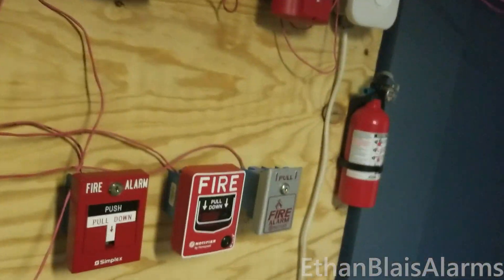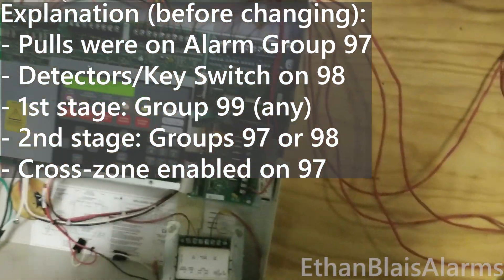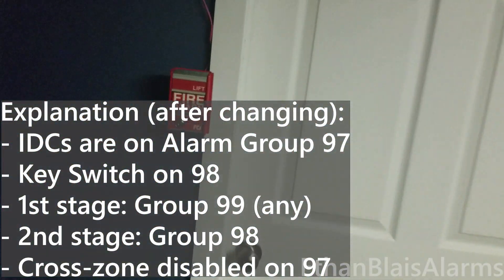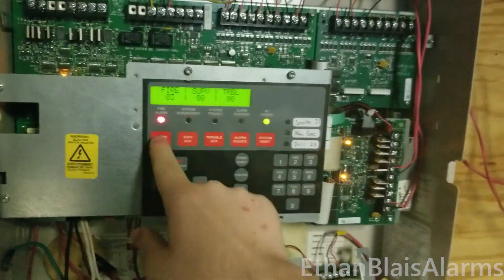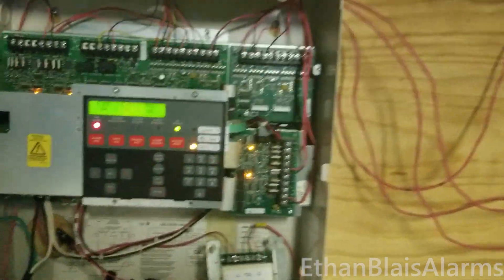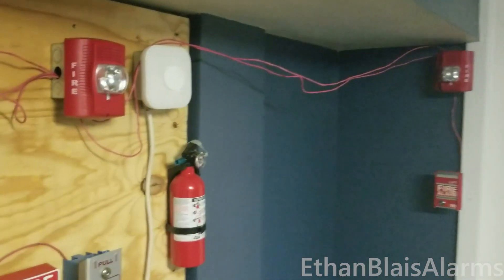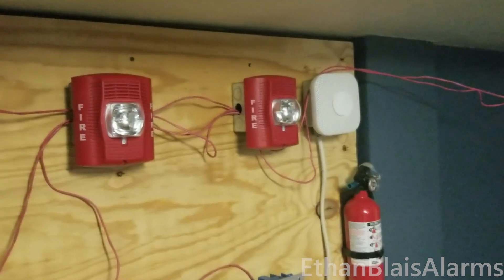Additionally, with my old programming I had it set up so that activating two pull stations would put it into second stage as well, but with this current programming it requires the key switch or drill to put it into second stage. But anyways, let's activate this pull station over here now. Ladies and gentlemen, your attention please — an emergency condition has been reported in the building. We are investigating the cause of the alarm. While we are verifying this alarm, please stand by. Alright, let's put it into second stage. Attention, this is an emergency announcement. A fire has been reported in the building. Please evacuate the building immediately using the nearest exit. Do not use elevators. Evacuate using the nearest exit.